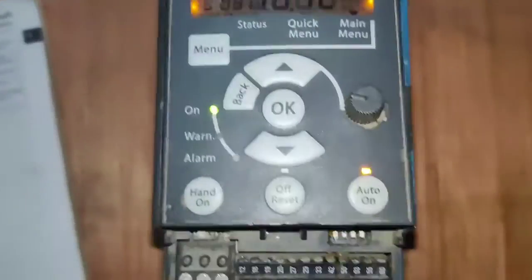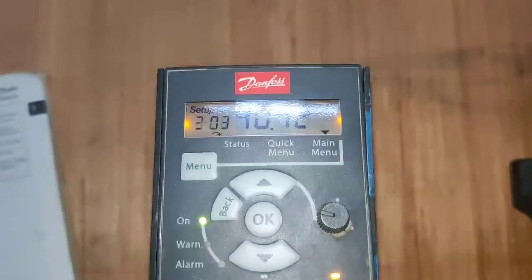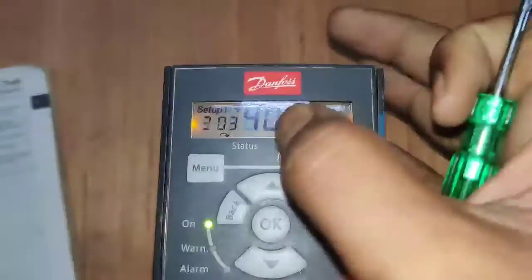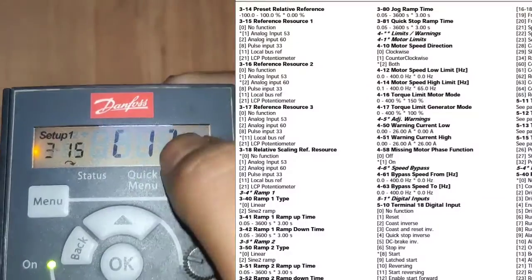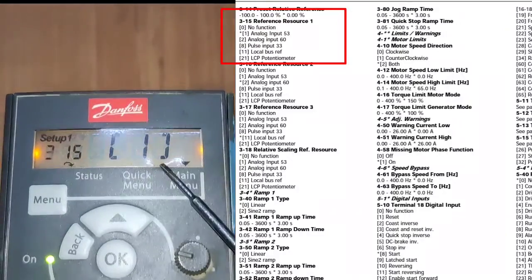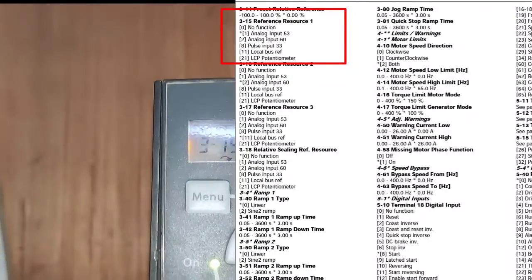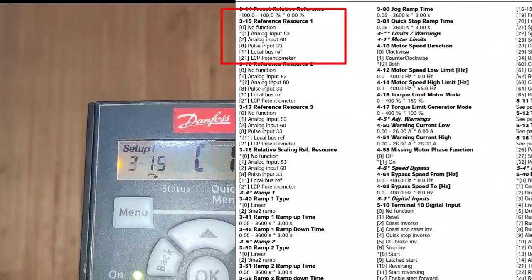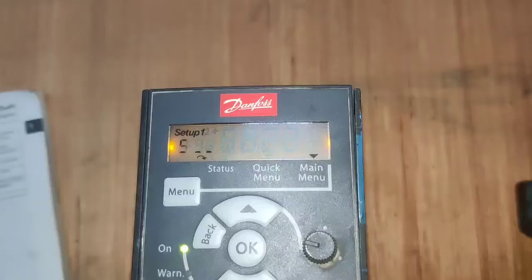Since we use terminal 53 as the analog input, go to parameter group 3, parameter 15 — this is for reference selection. Since we use terminal 53 as the analog input, set it to 1. If you want to use terminal 60 as the analog input, set it to 2. If you want to increase or decrease using the drive keypad, set it to 21.